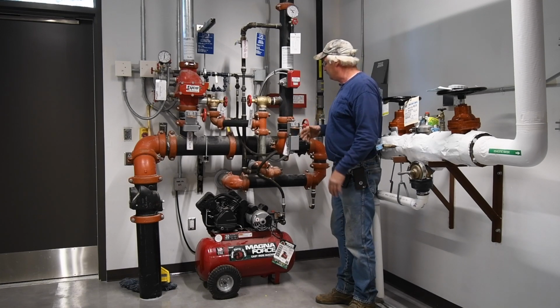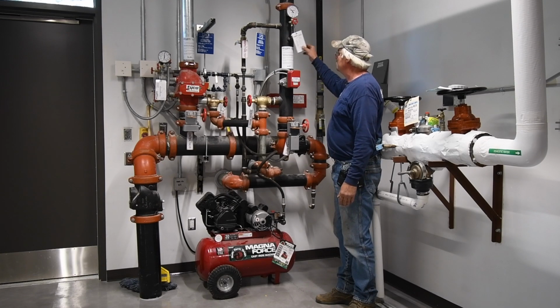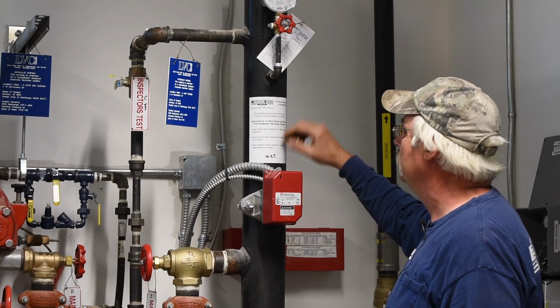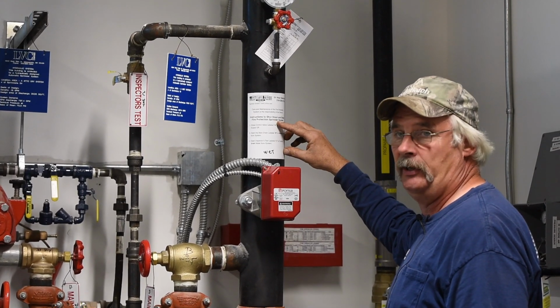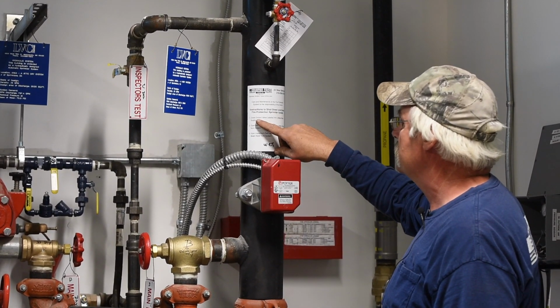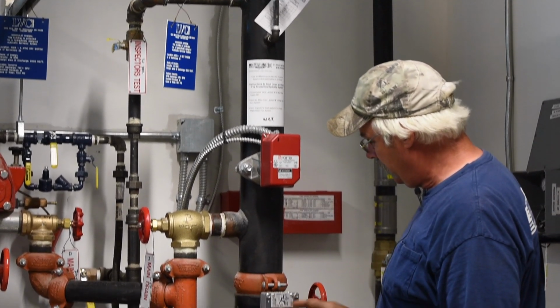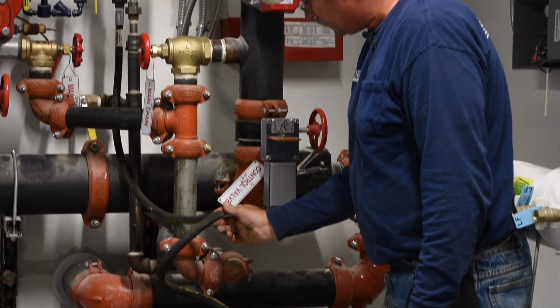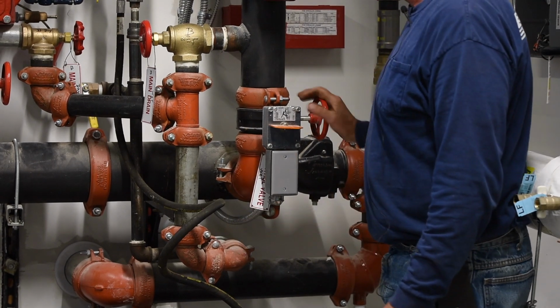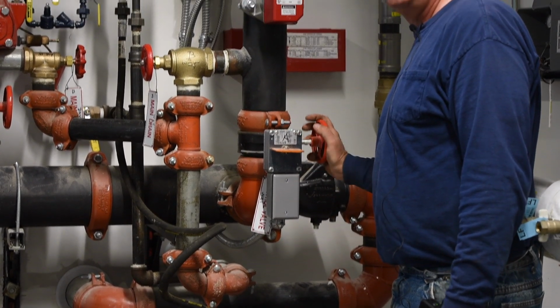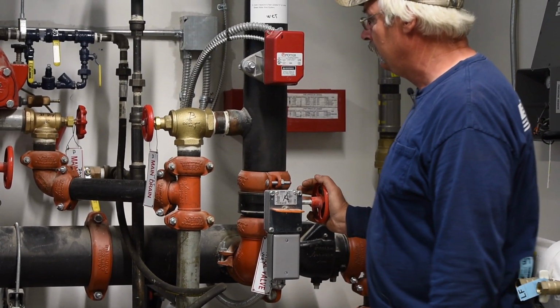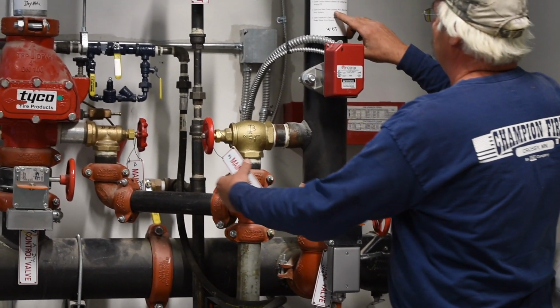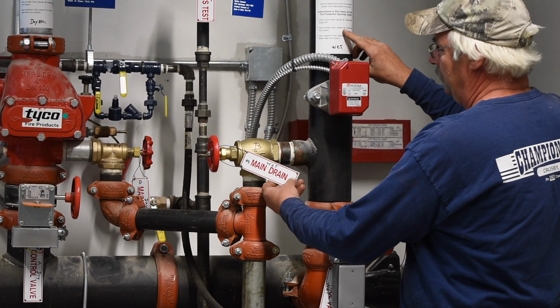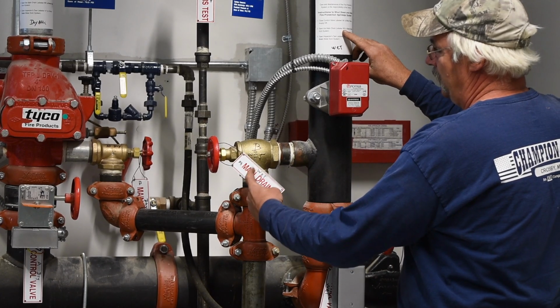If you have a fire, the head's going to go off, it's going to put the fire out. There's steps on each riser to shut a system down after a fire, to drain it down. Step one, close control valve labeled A, and we have a control valve that says wet labeled A. So you turn that clockwise till it's off, like it is right now. Step two would be open main drain B. So here's main drain B, wet.